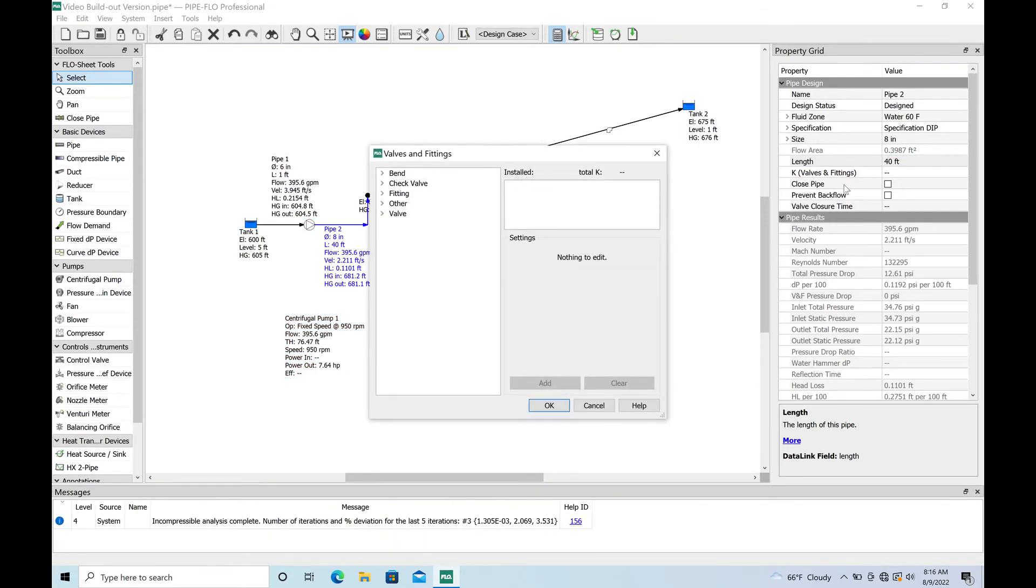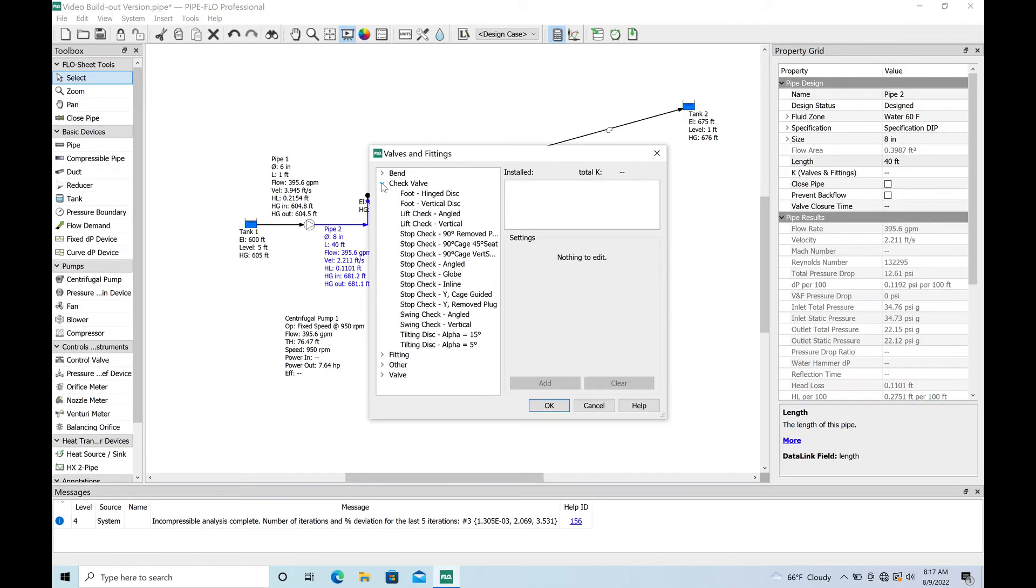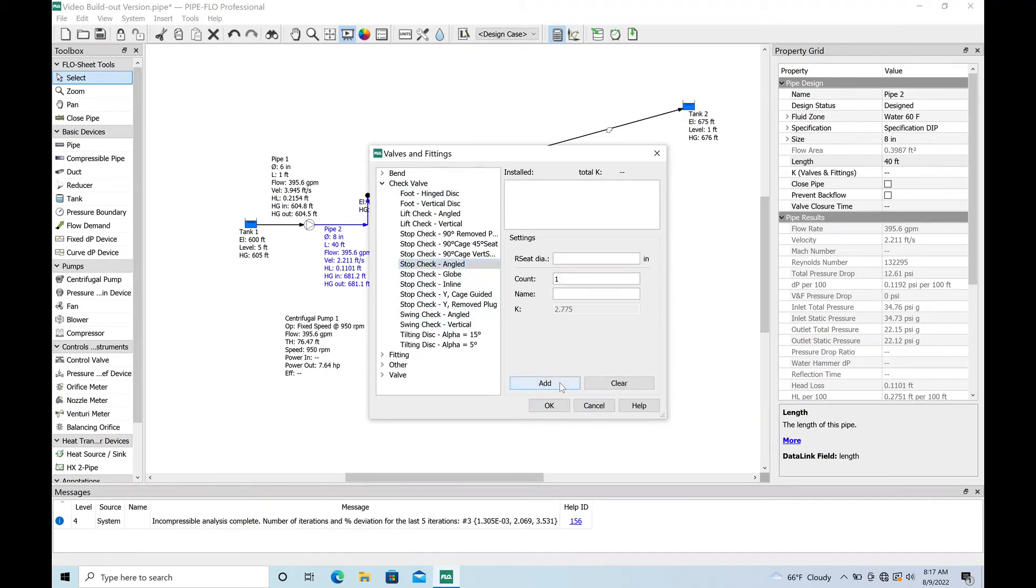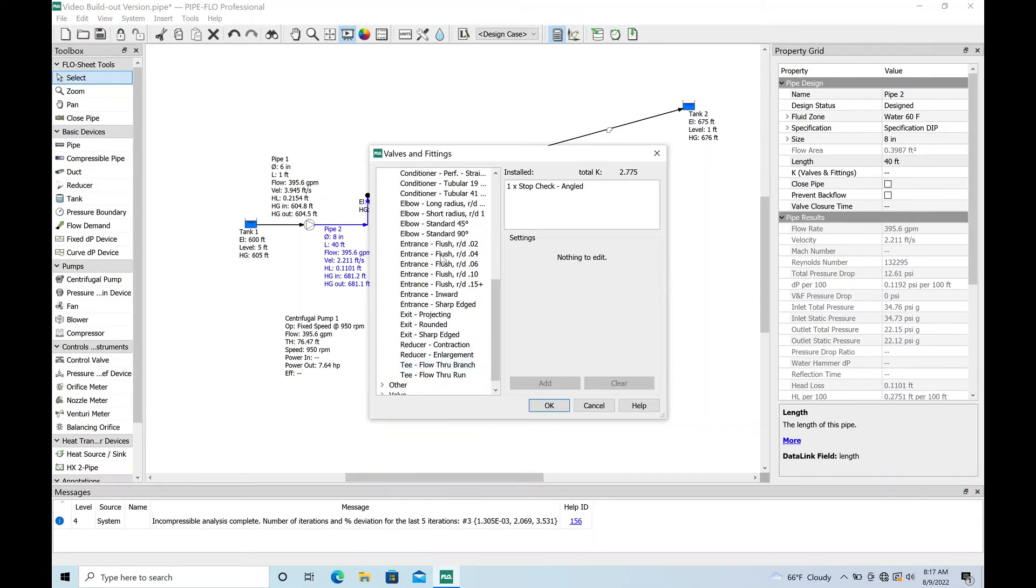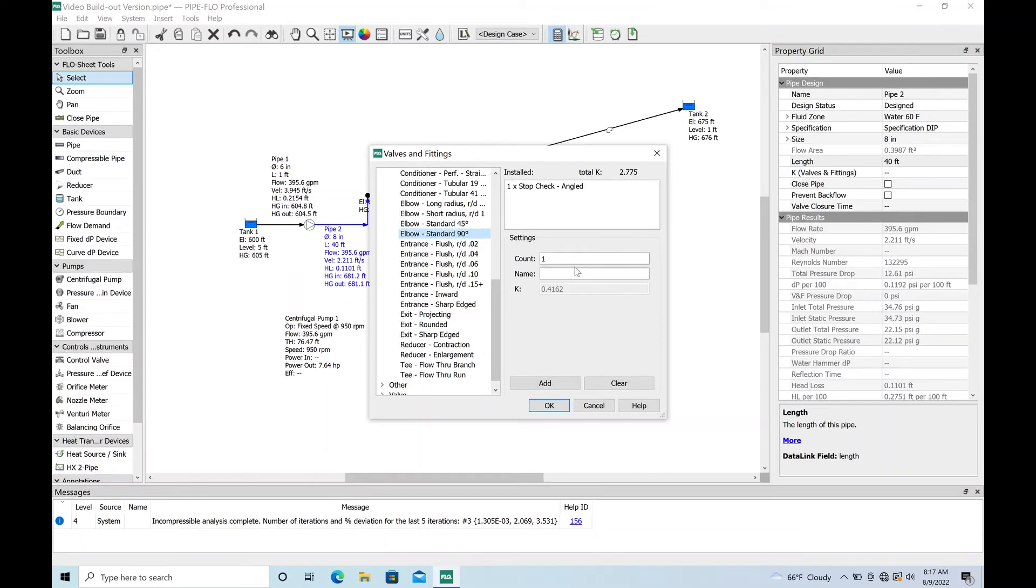Let's see here, check valve - stop check angled, that's a pretty standard unit. You can go to a manufacturer and get real K values for these as well. Let's throw in a couple of 90s just for the bends getting out of the wet well. Let's say there's like four of those.